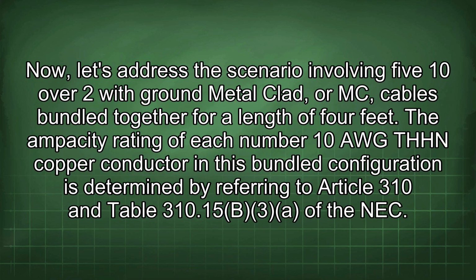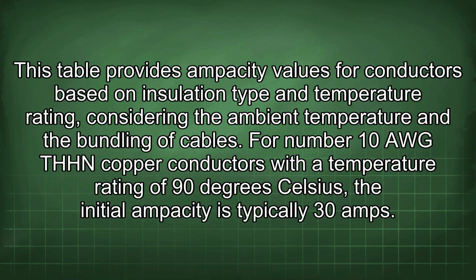Now, let's address the scenario involving 5 10/2 with ground metal clad, or MC, cables bundled together for a length of 4 feet. The ampacity rating of each number 10 AWG THHN copper conductor in this bundled configuration is determined by referring to Article 310 and Table 310.15(B)(3) of the NEC. This table provides ampacity values for conductors based on insulation type and temperature rating, considering the ambient temperature and the bundling of cables.